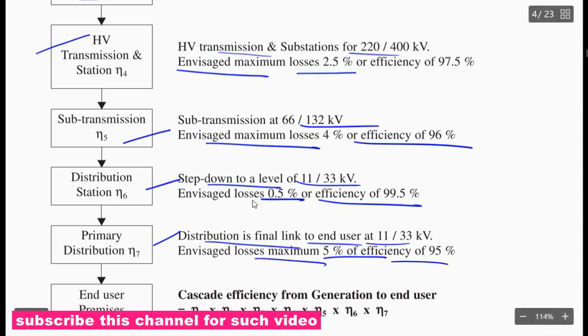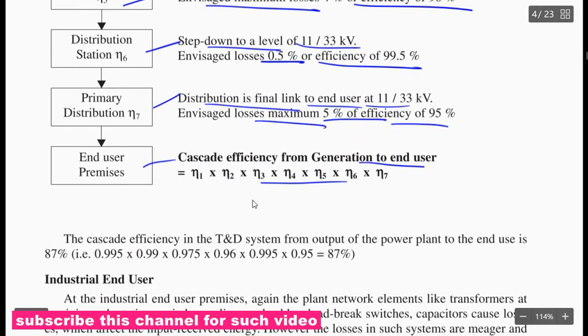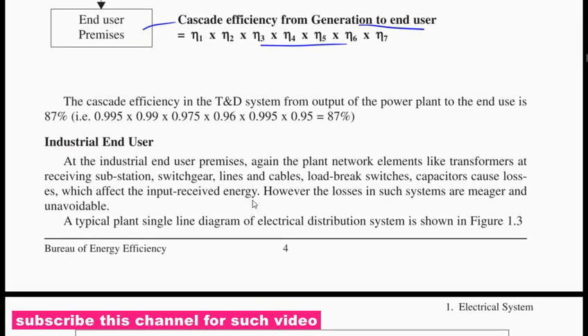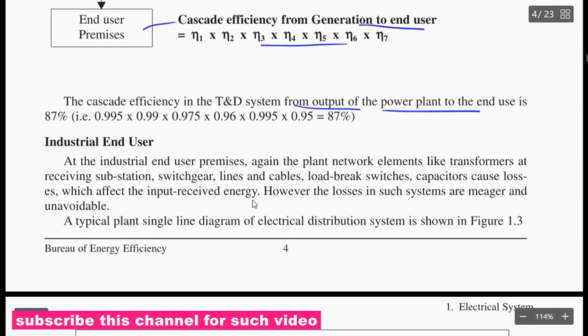Losses maximum 5% of efficiency, 95%. End user premises cascaded efficiency from generation to end user. That is cascaded efficiency. The cascaded efficiency in the transmission and distribution system from the output of the power plant to the end user is 87%: 0.995 × 0.99 × 0.975 × 0.96 × 0.995 × 0.95. That is 87%.